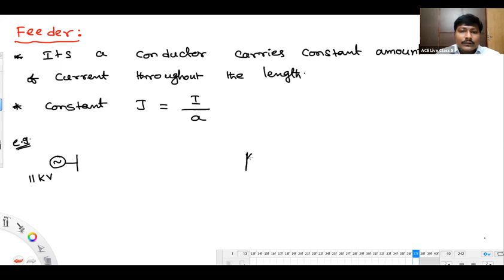Now, listen please. I want to interconnect this 11 kV generator bus to the 220 kV grid. How? Definitely, first I should use a step-up transformer of 11 kV by 220 kV. Then we have to run a 220 kV transmission line and connect that to the 220 kV bus bar. That's the connection you have to make. So first here, we'll keep one transformer of 11 kV by 220 kV, and then we are going to run a 220 kV transmission line connecting to this 220 kV grid. 11 kV by 220 kV transformer, step-up transformer.